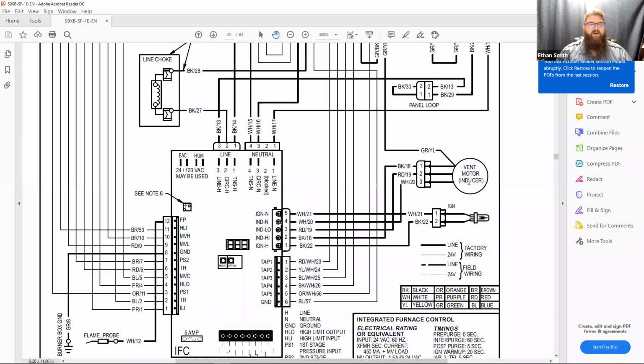So I can now take my meter, put it across these 2 terminals, either at the board where we have wiring designations, or at the inducer motor. Okay, so if I didn't know, for example, that my white was neutral and my red was my low speed, I could go to this diagram, see it there. Or if you are like several of my coworkers and are completely colorblind, you can look for the wire numbers at both ends and check for voltage. Okay, so there's something for everybody here.